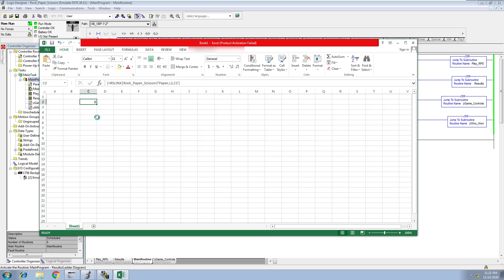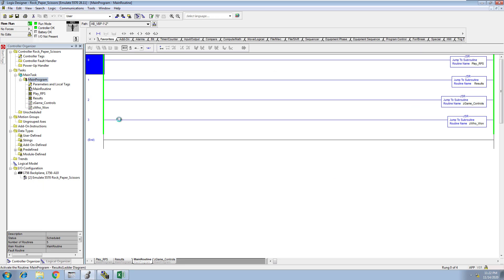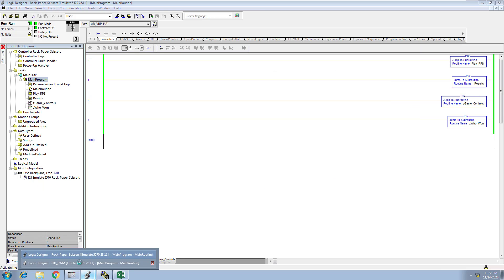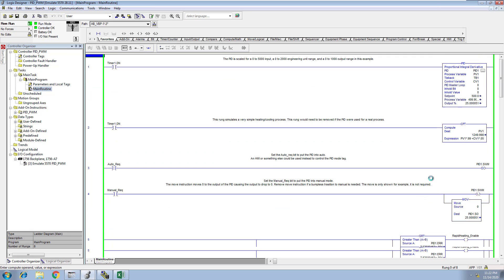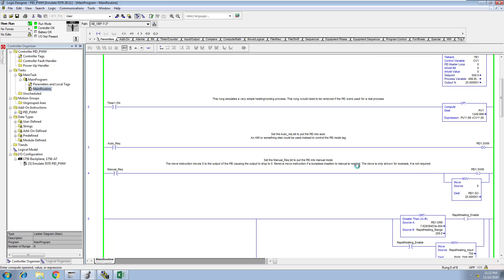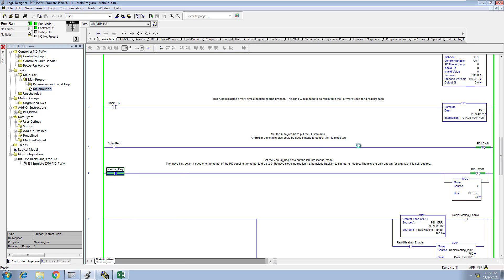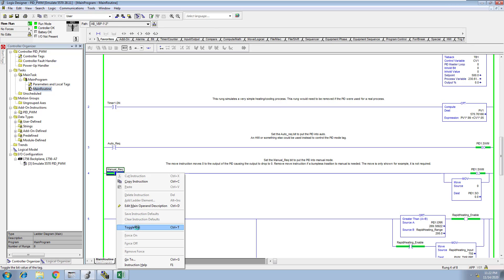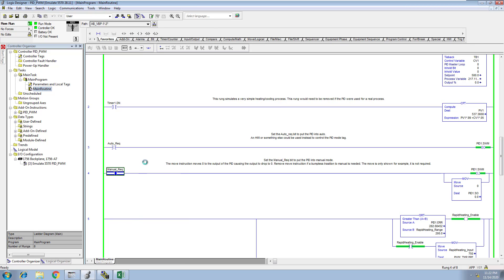Let's do another one. Let's do the PWM, which is the PID loop that continuously goes up and down. Let's actually throw this in manual real quick so you can see it fluctuating, and we're going to throw this PV off a little bit so you can see the CV and everything working properly. Then we're going to take it out of manual and put it back into auto.